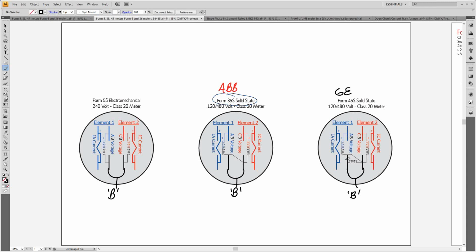As I look at this one with B phase jumpered across the bottom, there's a potential coil in the 45S connected between these two, but having this jumper here really nulls that out. Even though there's a potential coil there, both sides of the potential coil have the same voltage on them, so this has no effect in the metering. And so A to B voltage is across one potential coil, same as the 35S, and C to B across the other potential coil, same as the 35S. That's how we would replace a 5S with a 45S.